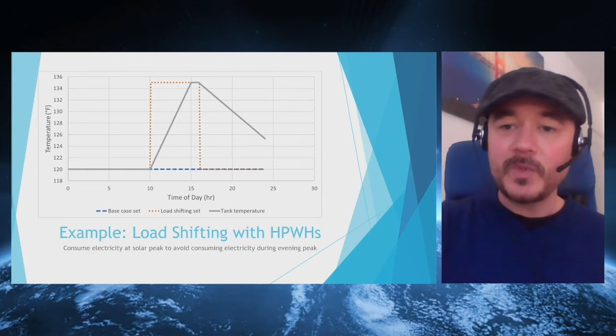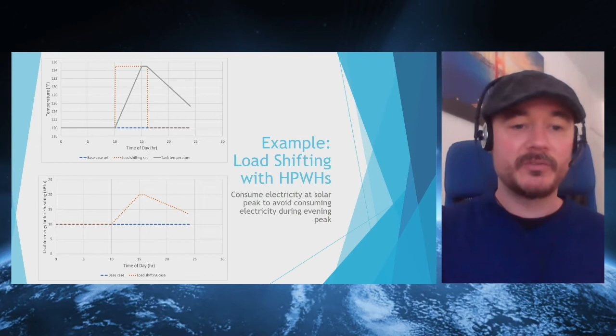This next slide shows why we're doing that. The second plot on the bottom shows the amount of energy that can be withdrawn before the water heater has to heat water, assuming a set temperature of 120. From 10 a.m. to 3 p.m., the amount of energy that can be withdrawn before having to heat the water gradually increases until it's roughly double the amount as in the base case, and then it holds steady until 4 p.m. as we maintain that 135 temperature.